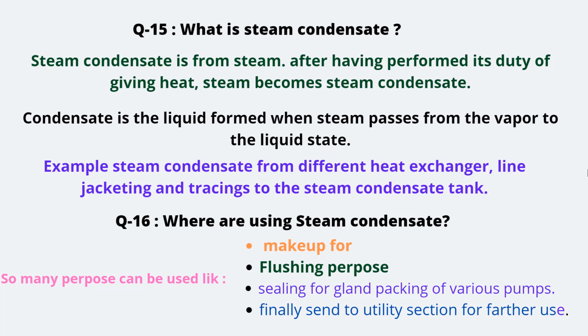Example: steam condensate from different heat exchangers, line jacketing and tracing goes to the steam condensate tank. Why are we using steam condensate? It can be used for many purposes, like makeup, flushing, and sealing for the gland packing of various pumps, and it is finally sent to the utility section for further use.